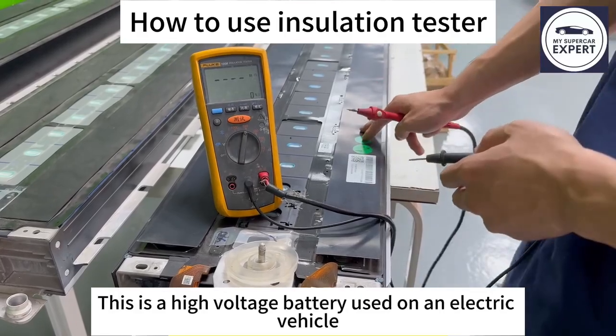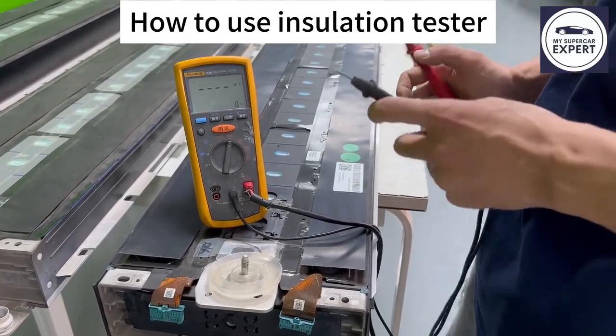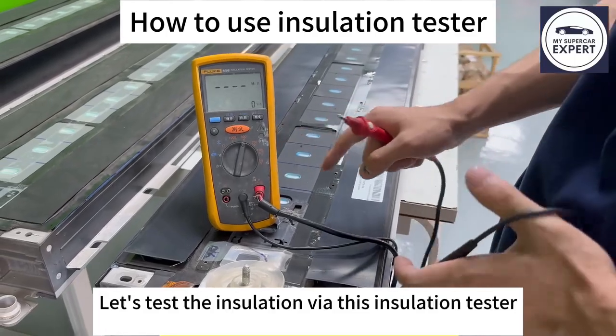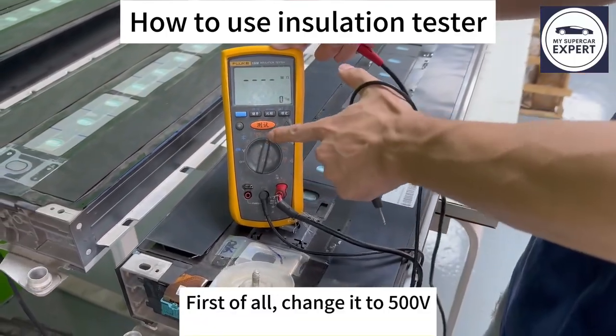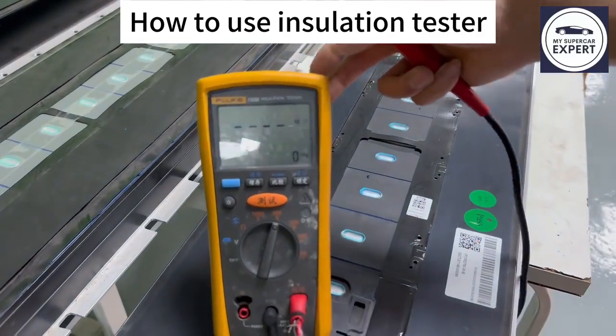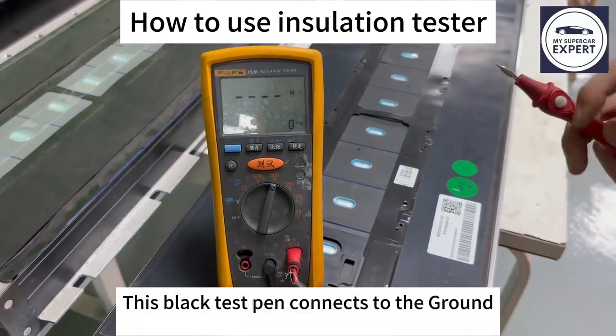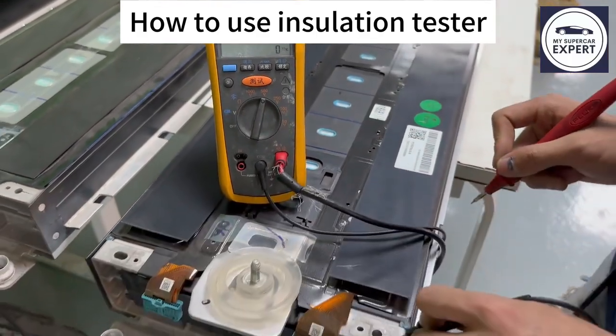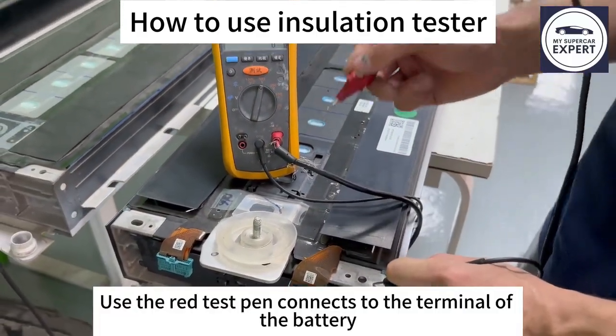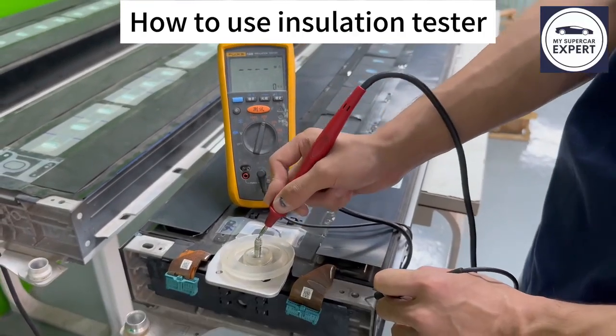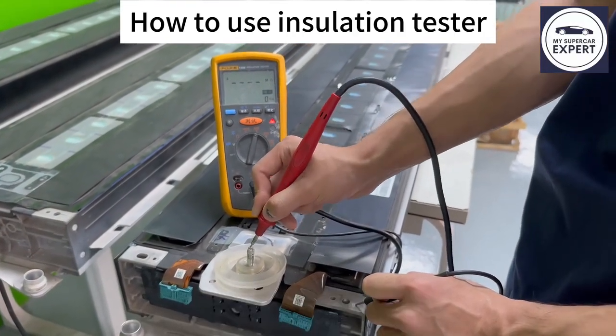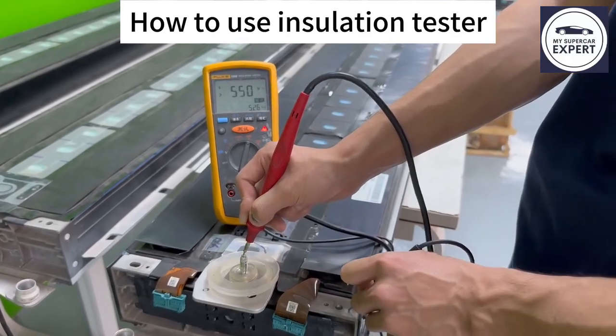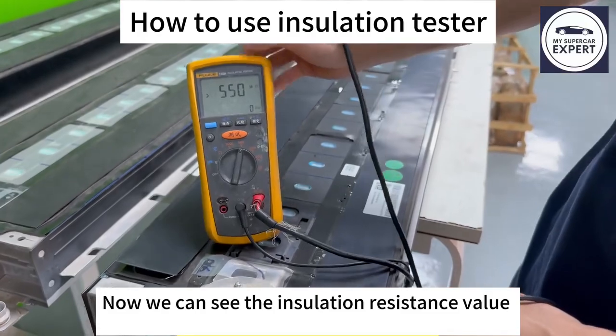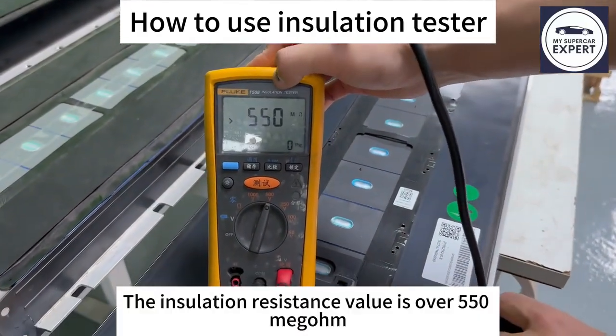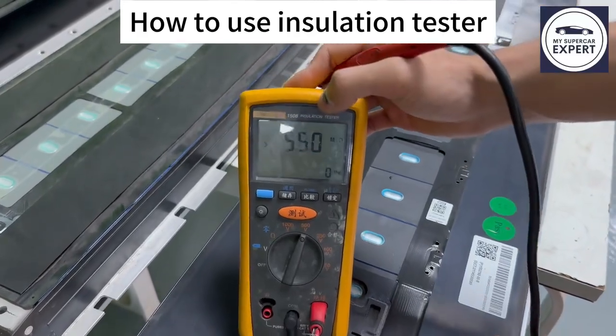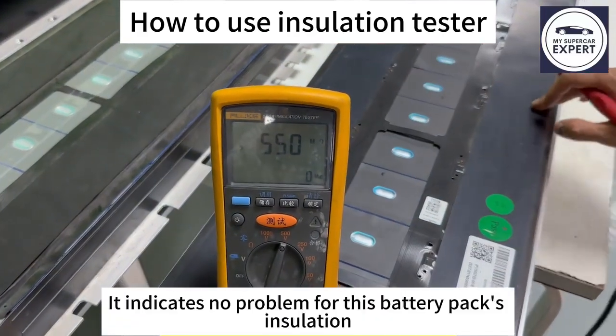This is a high voltage battery used on an electric vehicle. Let's test the insulation with this insulation tester. First of all, change it to 500 volts. After that, this black test pen connects to the ground. The red test pen connects to the terminal of the battery. Then press this test button. Now we can see the insulation resistance value. The insulation resistance value is over 550 megohm. It indicates no problem for this battery pack's insulation.